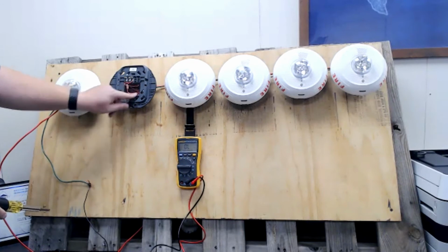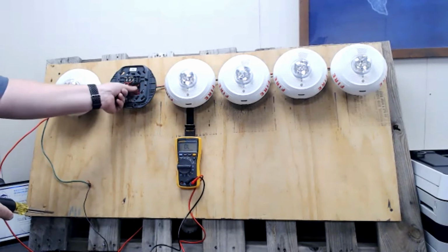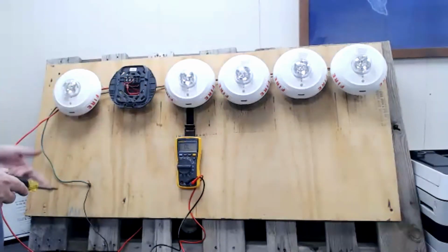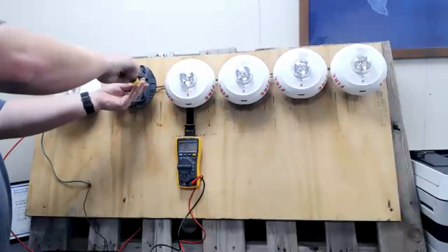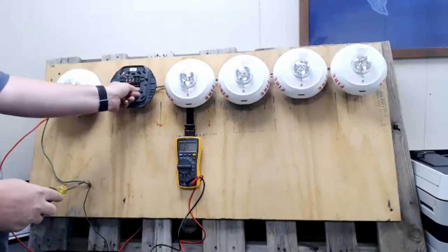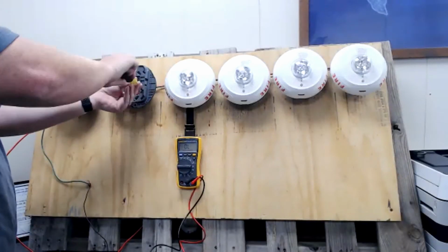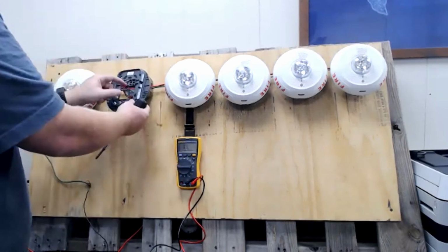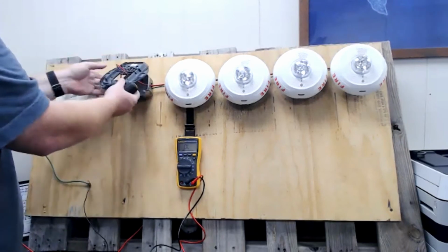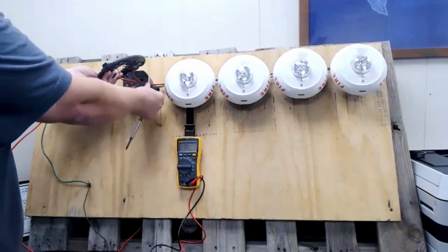And when I pull on it, this black conductor won't come over. It seems like it's pinched. So there's a good chance that's my ground fault. So I'm going to go ahead and loosen up my base. Oh, that was definitely my ground fault. See, I got some bare copper here. It was pinched.